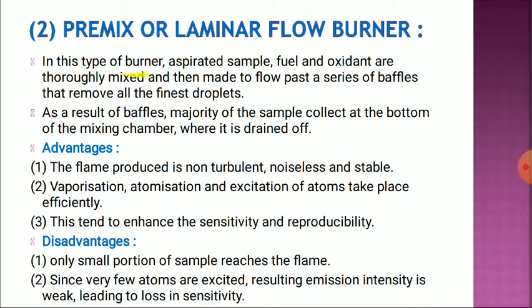In this type of burner, aspirated sample, fuel and oxygen are thoroughly mixed and then made to flow past a series of baffles that remove all the finest droplets. As the result of the baffles, the majority of the sample collects at the bottom of the mixing chamber where it is drained off. Now we will see the figure of this premix or laminar flow burner.